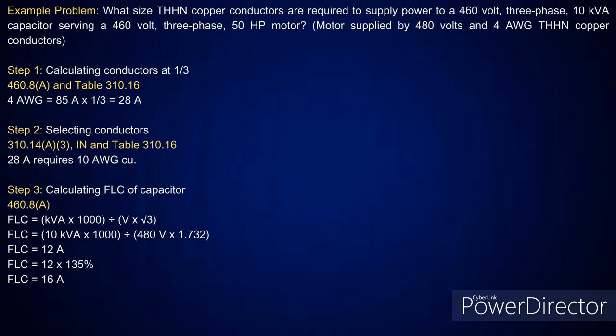All right. So in this case, I was at 28 amps. I go over to Table 310.16. The next size above that's 30 amps, which is a number 10. Now, that's doing the conductors at a third. Now, also in 460.8(A), I'm going to be looking at calculating the full load current of the capacitor. It's just like doing a transformer, generator, or anything else. I need to get the kVA of the capacitor, take it at 1,000, then divide it by the voltage. In this case, I have 480 volts times 1.732 for the three phase, going to give me 831 volts divided into that 10,000, and that's going to give you 12 amps. But it tells you there that you also have to take it at 135%, which is going to give me 16 amps. Okay? Right.